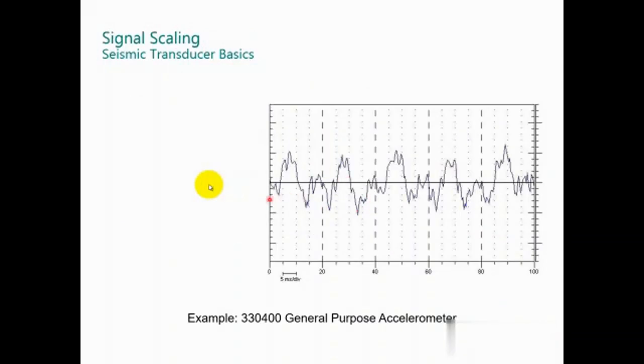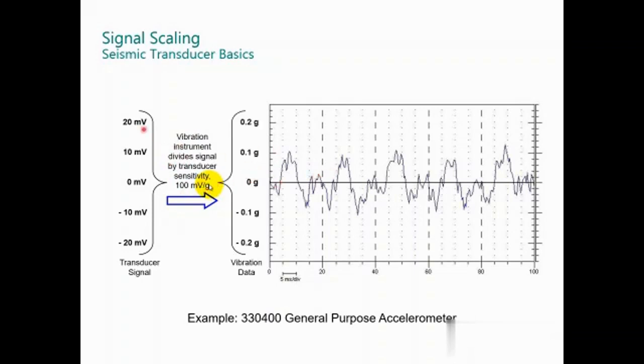From the basics, we have this signal, a complex signal from the seismometer, which corresponds to an electrical signal. The maximum in this case is 20 millivolts to minus 20. Then the software and the monitor convert this electrical signal into vibration data using the scale factor. Here, dividing by 100 millivolts per g, 20 millivolts corresponds to 0.2 g's, minus 20 millivolts corresponds to minus 0.2 g's. And now, this plot represents digitally the vibration captured by the transducer.